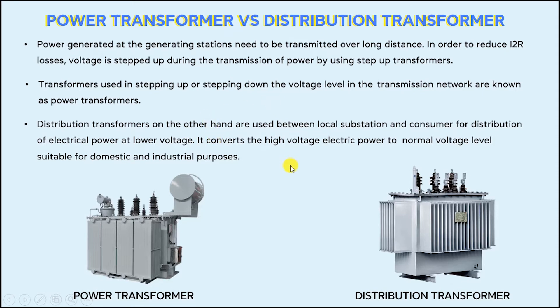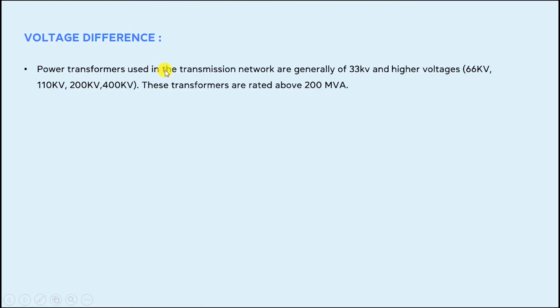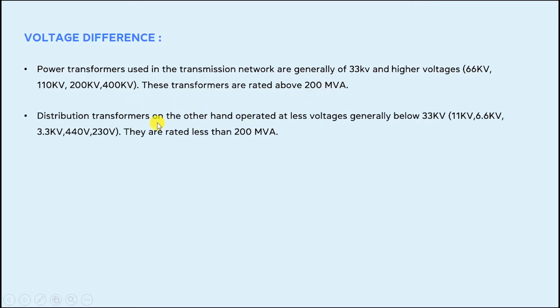Now let's discuss the other differences between power transformers and distribution transformers in detail. The first point is the voltage difference. Power transformers used in the transmission network are generally rated at 33 kV and higher voltages, and are rated above 200 megavolt-ampere. Distribution transformers, on the other hand, operate at lower voltages — generally below 33 kV — and are rated less than 200 megavolt-ampere.